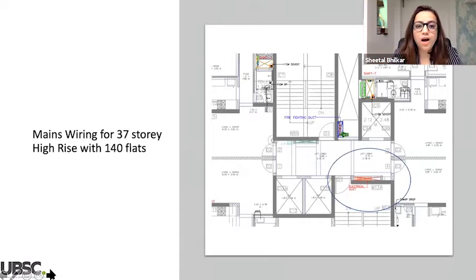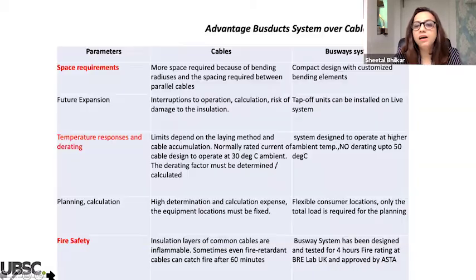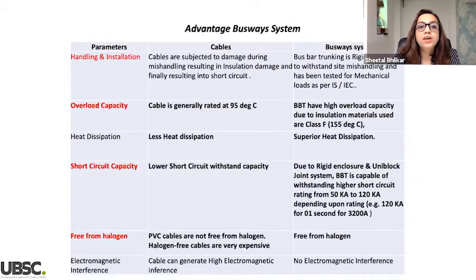So in a cramped duct, you can't take 140 cables together, it is a fire hazard. So instead of that, if you go for a bus duct, rising mains, that saves space also, and it is a very superior product than cable. Space requirement is less, then temperature response and derating in case of bus duct is much superior. Fire safety wise also bus duct is much superior. Then installation time is very much less in case of bus duct over the cables. Even overload capacity of bus duct is much more. It can take up to 150 degrees Celsius. Even short circuit capacity of a bus duct is good.